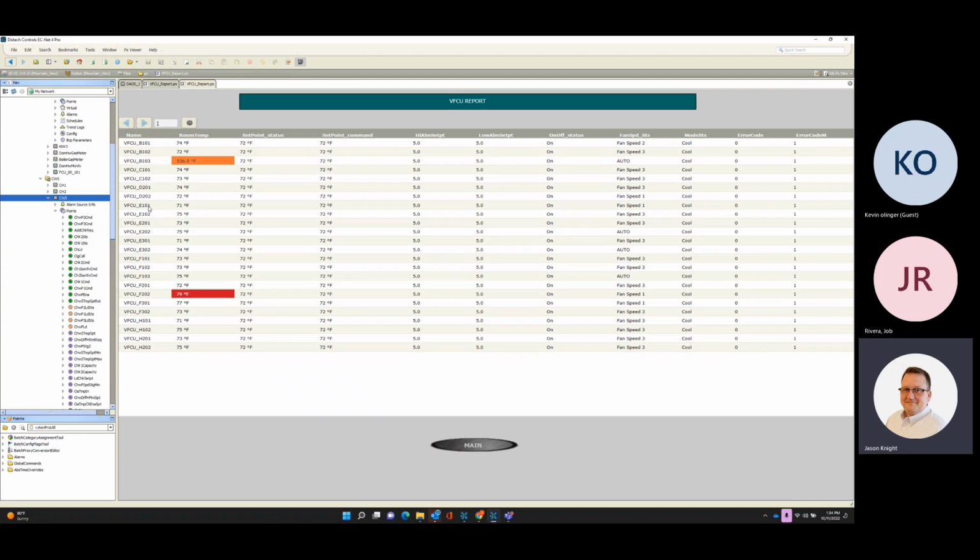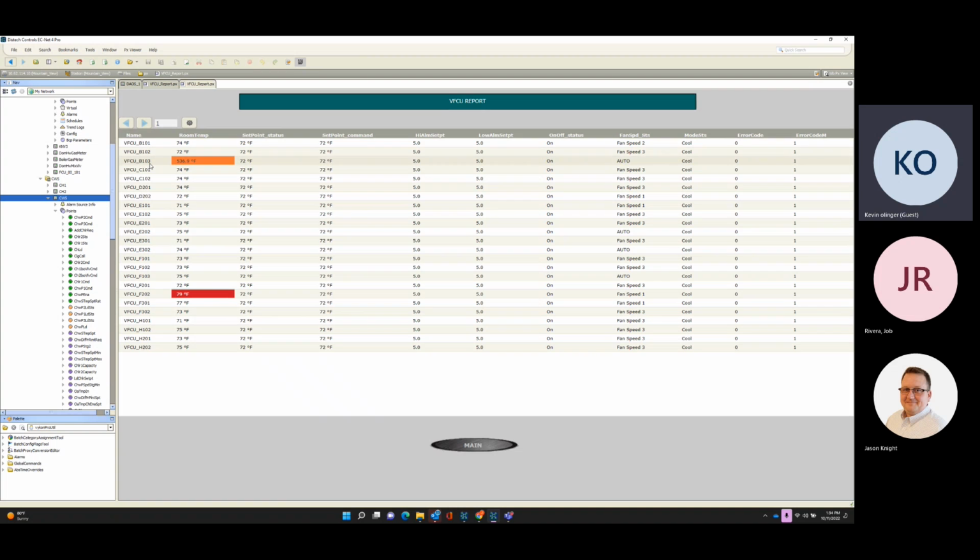Yeah, it's because somebody left DOAS 6 overridden on. And so I confirmed last week, Friday evening, that everything's shut down, the plant's shut down. So I don't know if it was during commissioning or whatever, somebody overrode it on. So a DOAS, okay, interesting.